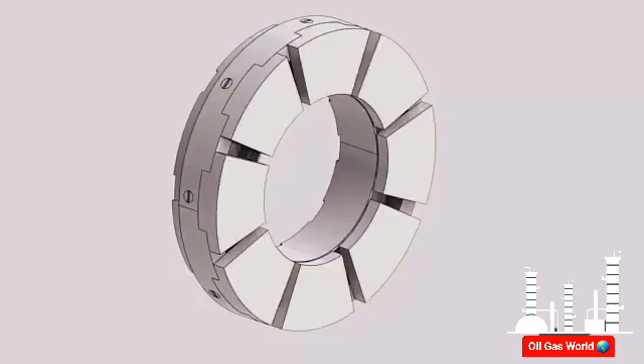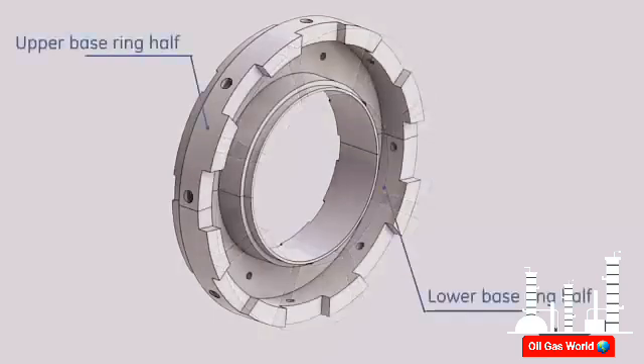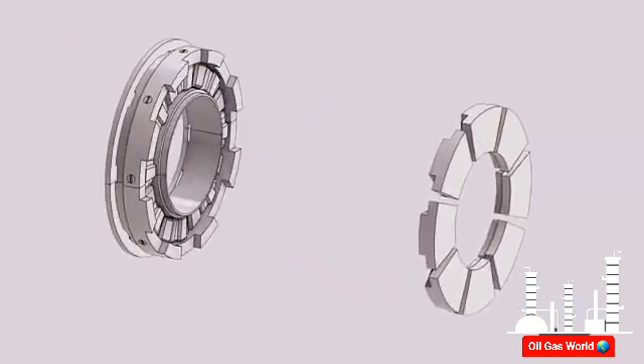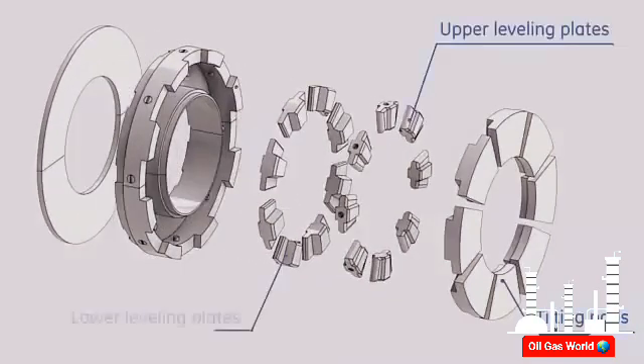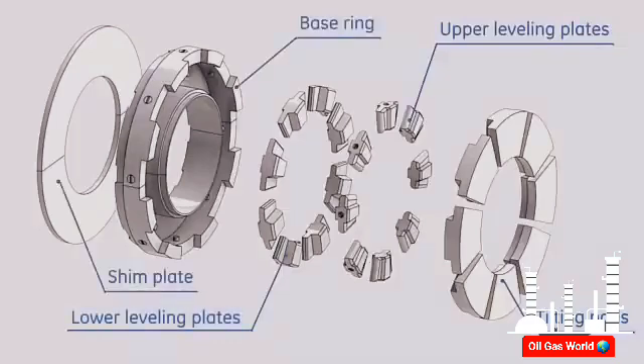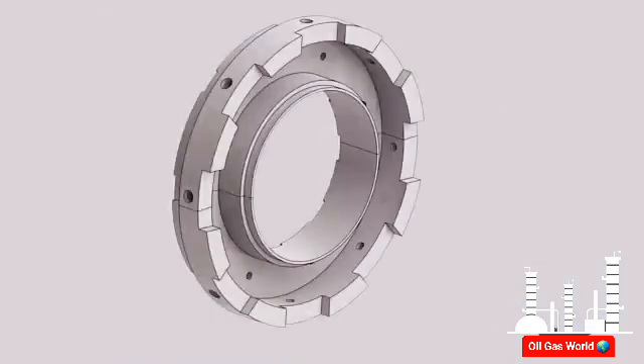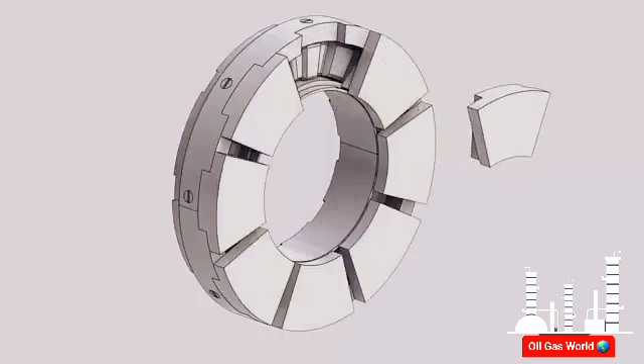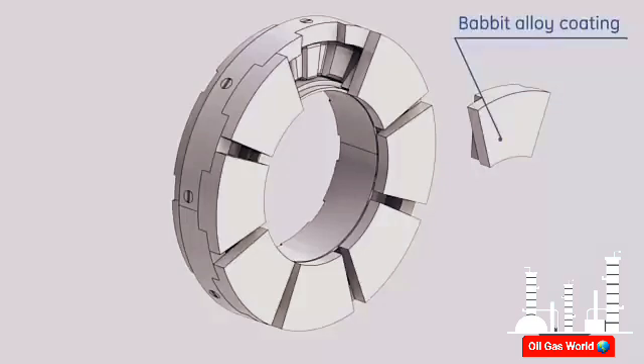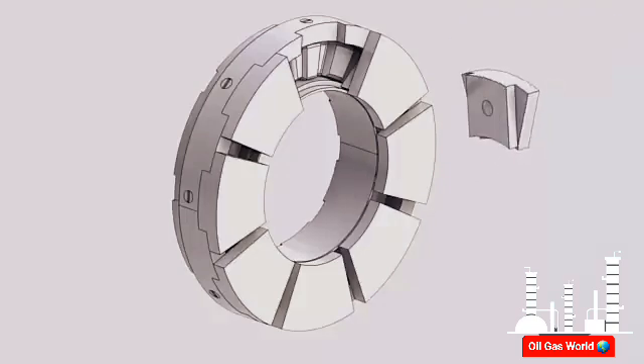The main components of this bearing are the base ring. The base ring provides support for all parts of the bearing assembly and keeps parts in the proper location. The pads are shaped like a sector of a ring. The bearing surface is covered with Babbitt alloy. Every pad has a hardened steel button on its back called the pad support. This pad support allows the pad to tilt slightly in any direction.